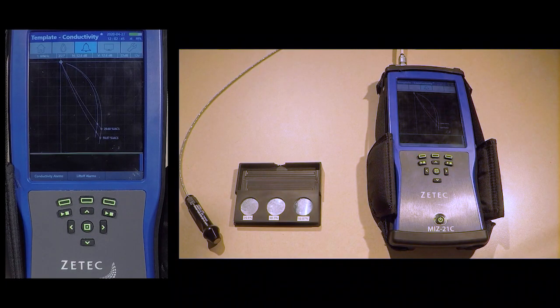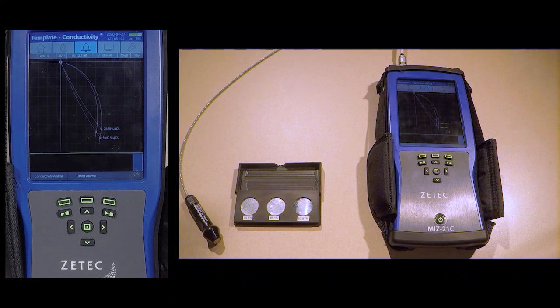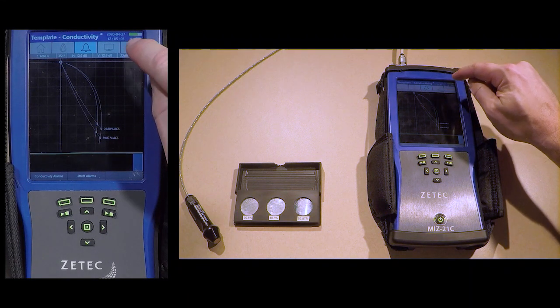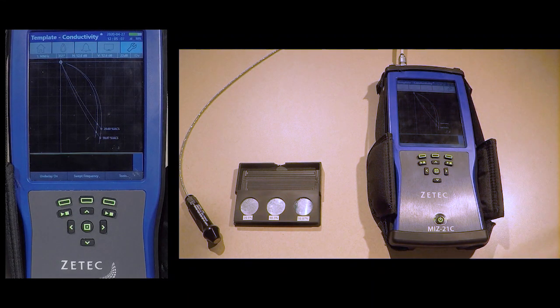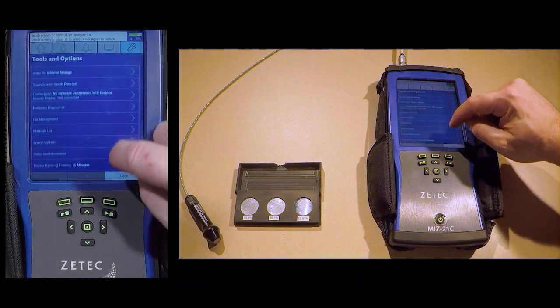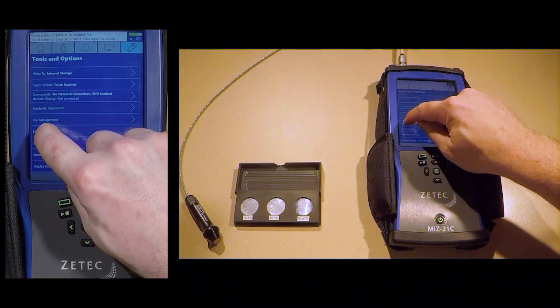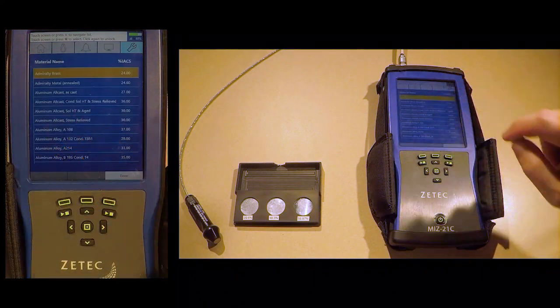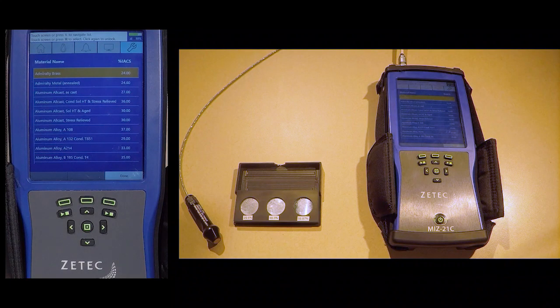To access the materials list if in acquisition mode, press the Stop Play button to stop the acquisition. Select the Tools icon in the upper right corner. Tap Tools in the lower right corner. Use your finger to slide the menu up and tap Materials List. A list of materials is displayed with defined IACS specifications to assist in setup for your specific use.